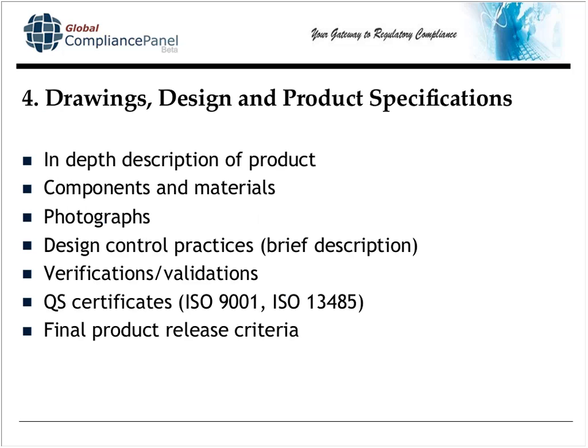Section four of the technical file is the more product-specific information: an in-depth description of the product, all of the components and materials. Some firms choose to put photographs in their technical files. A brief description of your design control practices — you can't just reference your SOP, but several sentences on how you design control, whether you go by phase gate and what your phases are. Any verifications or validations are a great opportunity to reference by validation number, if that's how your company does that. Your notified body will want to see your final product release criteria — that's the QA inspection of the finished device.